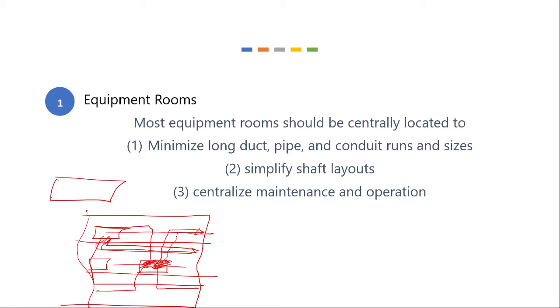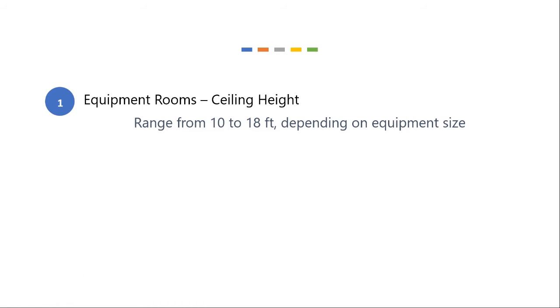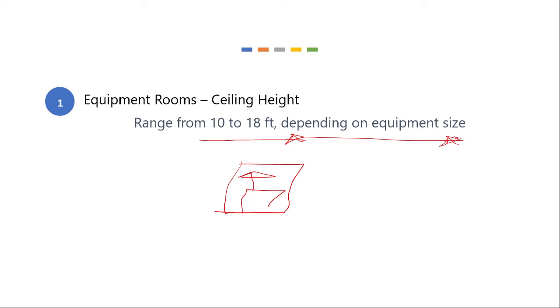as possible. We want to also simplify the shaft layouts, and we want to be able to centralize our maintenance and operations. So it should be easy for maintenance to access all the equipment that could break down and fix it. So consider a ceiling height for your room from 10 to 18 feet, and that depends on equipment size. And also consider future equipment. Even if the equipment that you're installing now doesn't need that much of a ceiling height, 5 or 10 or 20 years from now, things might change. So having the extra space can be helpful.